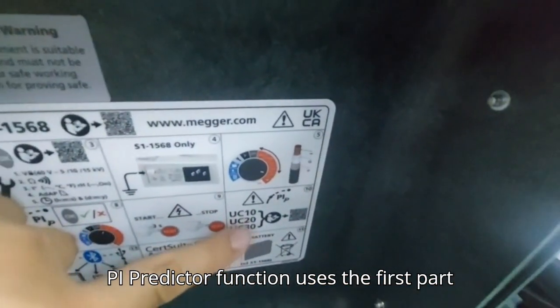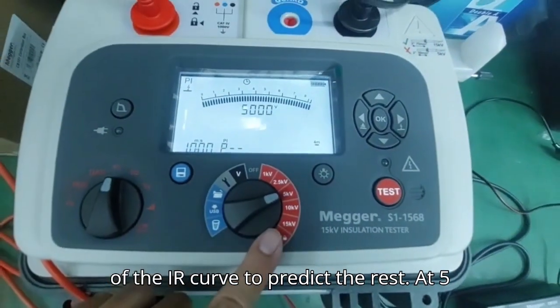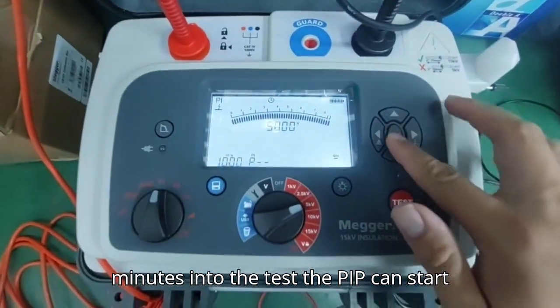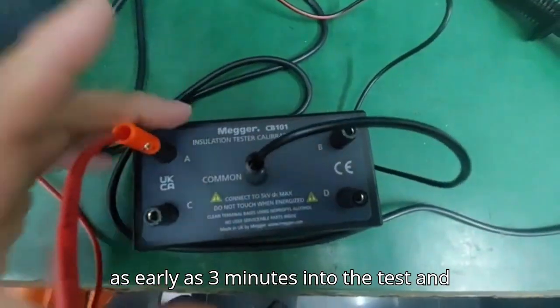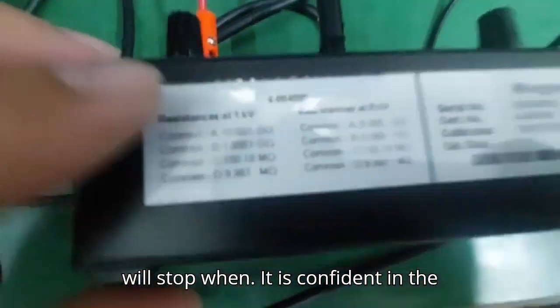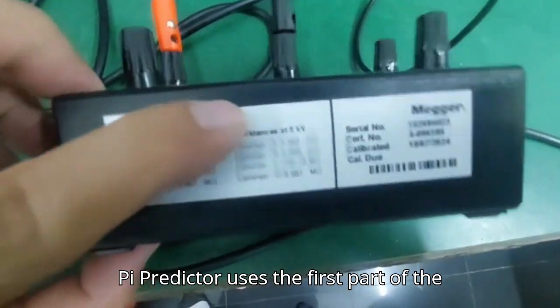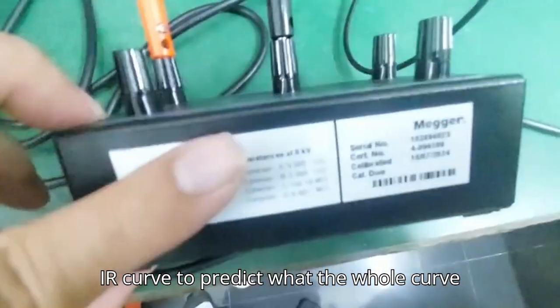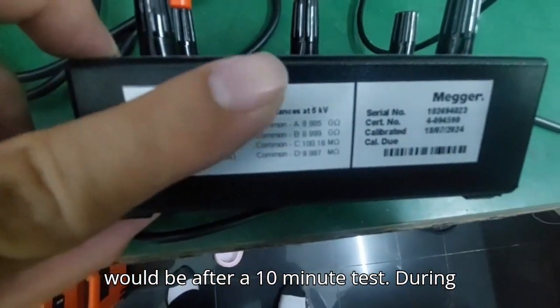The PI predictor function uses the first part of the IR curve to predict the rest. At 5 minutes into the test the PIP can start as early as 3 minutes into the test and will stop when it is confident in the prediction. PI predictor uses the first part of the IR curve to predict what the whole curve would be after a 10-minute test.